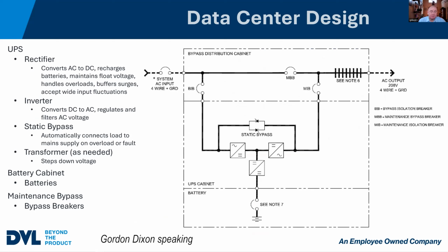A UPS has some primary components, like the rectifier. So when you're bringing the power in, you're essentially converting it from AC power to DC power and then back again. Little caveat: not all UPSs do it that way. There are different methods; some just have AC feed all the way through with a DC feed charge in the background that will take over. But generally speaking, most large UPSs are going to transfer from AC power to DC and then back again. That way you've got a continuous charge through the batteries, but it also helps you have instantaneous crossover if there's a power outage. So the rectifier does that.